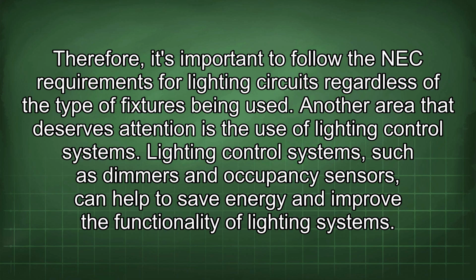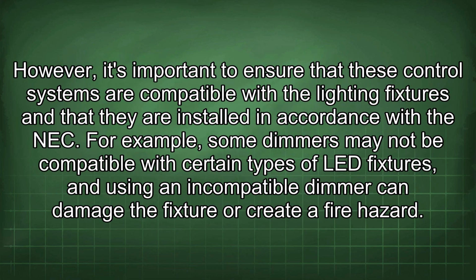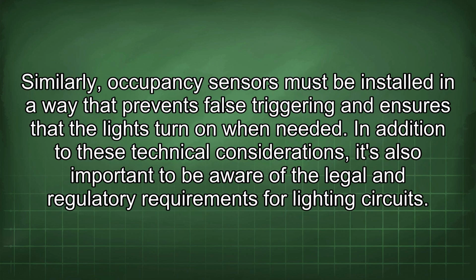Another area that deserves attention is the use of lighting control systems. Lighting control systems, such as dimmers and occupancy sensors, can help to save energy and improve the functionality of lighting systems. However, it's important to ensure that these control systems are compatible with the lighting fixtures and that they are installed in accordance with the NEC. For example, some dimmers may not be compatible with certain types of LED fixtures, and using an incompatible dimmer can damage the fixture or create a fire hazard. Similarly, occupancy sensors must be installed in a way that prevents false triggering and ensures that the lights turn on when needed.